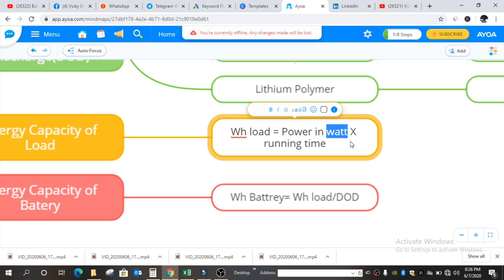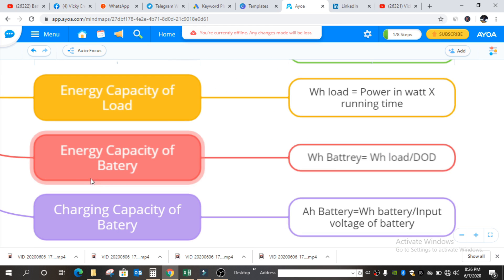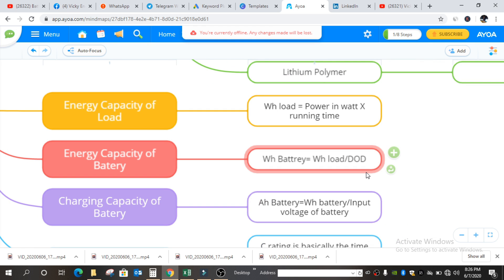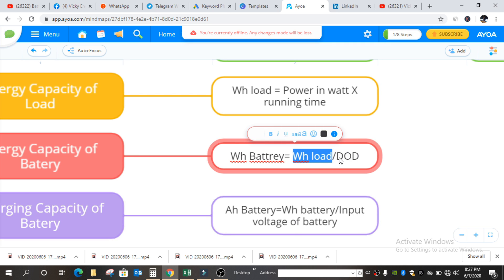If you don't know how to calculate your electrical load sheet, I am giving the link in the card button so you can go through. Also, if you have some query on UPS, I will give the UPS explanation link in the card button as well. Next is energy capacity of battery — the WH capacity of battery equals WH capacity of load divided by the DoD, which is the depth of discharge.